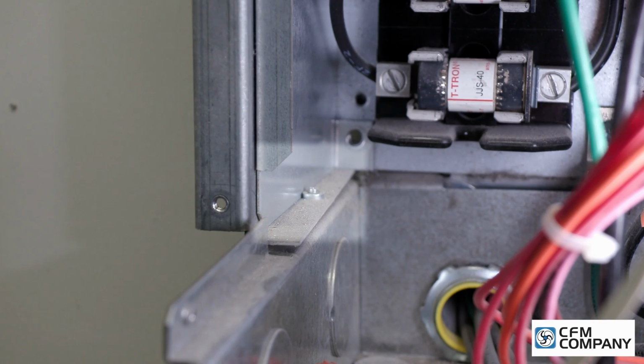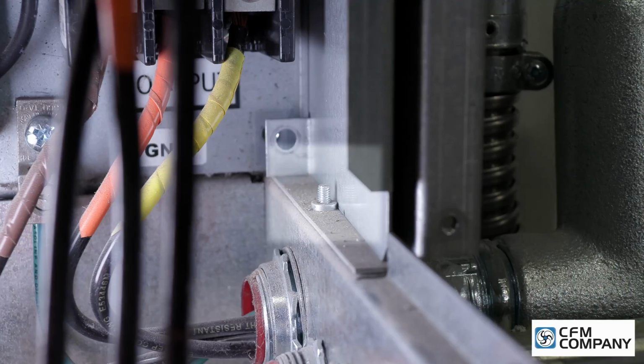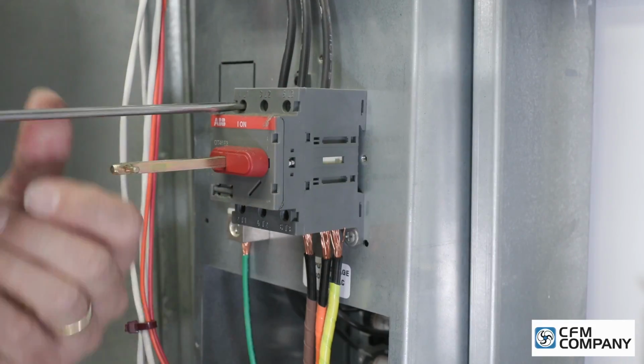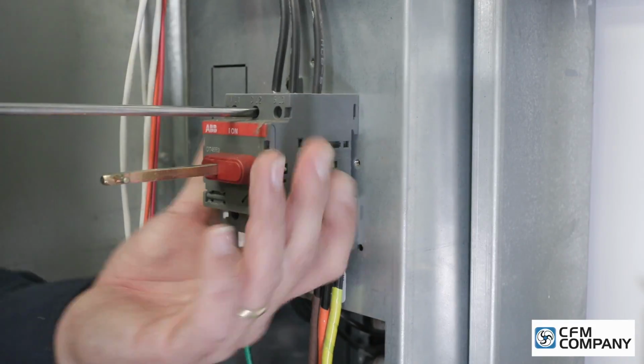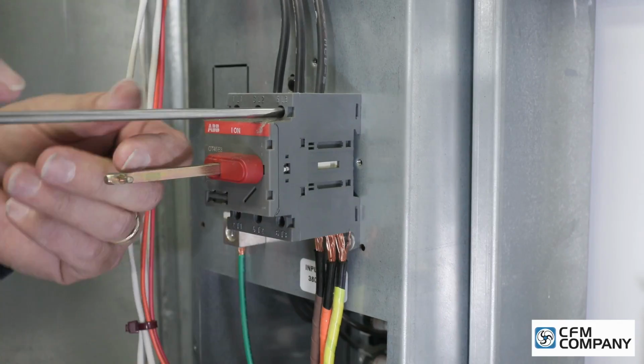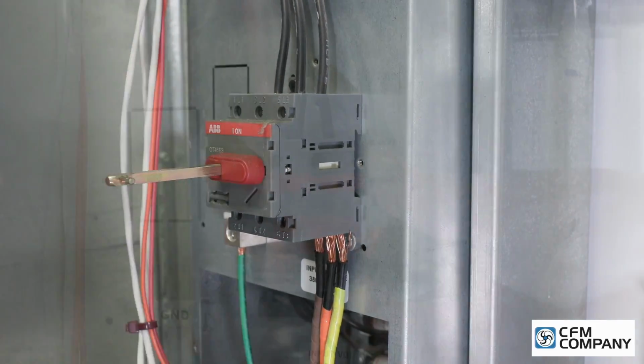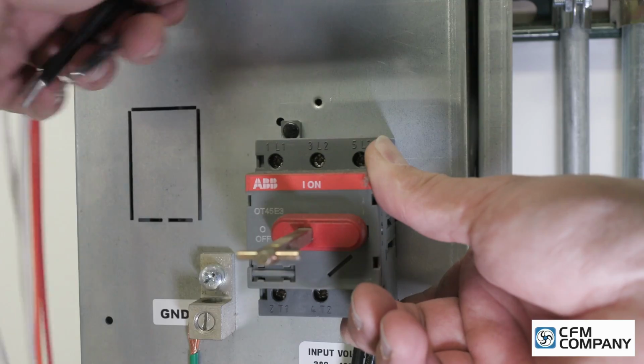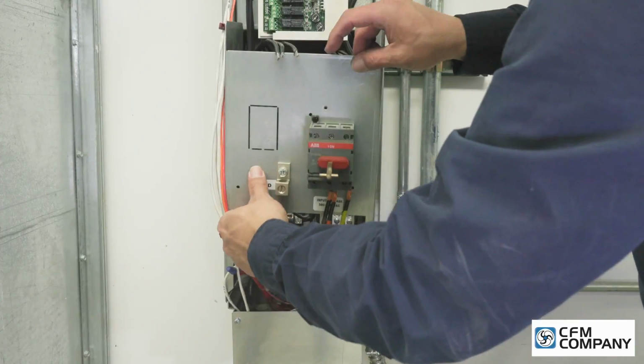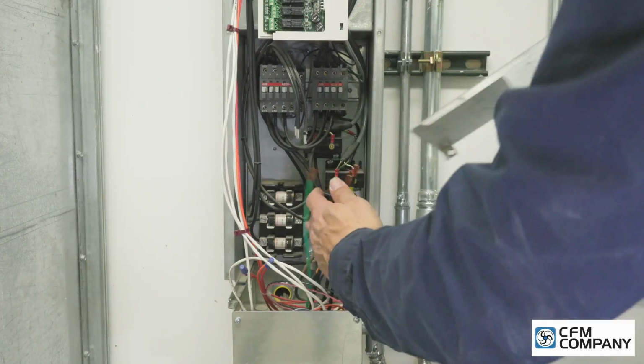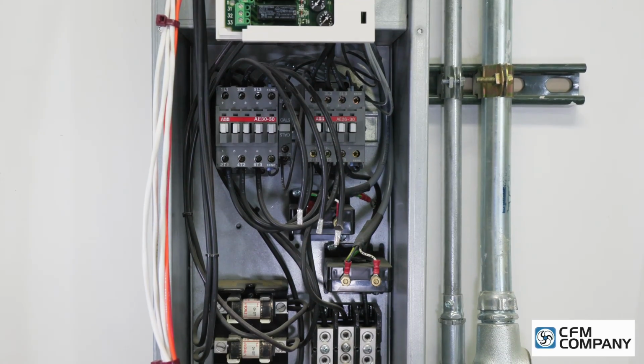The two screws that hold the bottom conduit box to the enclosure may need to be backed out to allow the metal tabs of the front disconnect plate to slide past. Remove the line side power wires from the main disconnect. Carefully remove the front disconnect plate, keeping clear of the control wires that may run in front of the plate.